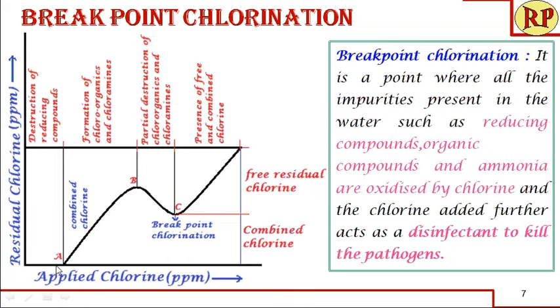Beyond A up to B, the curve increases, showing residual chlorine as applied chlorine increases. This is due to the formation of chloro-organics and chloramines — that is, organic impurities and nitrogen compounds like ammonia and urea form chloramines. This is reflected as increasing residual chlorine from A to B. We call this combined chlorine because the chlorine is in combined form — as chloro-organics and chloramines — not as free residual chlorine. So up to B, the chlorine is in combined form.